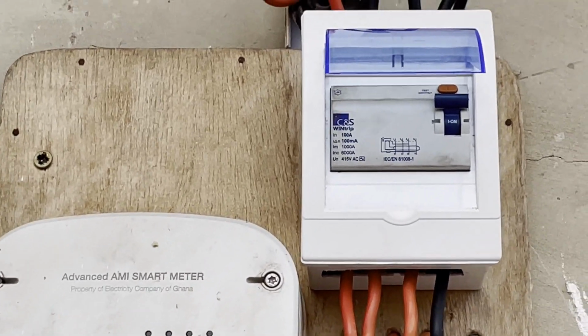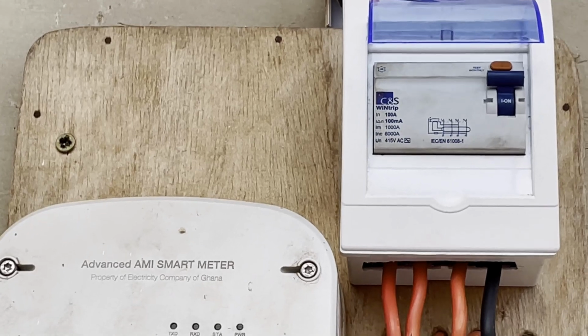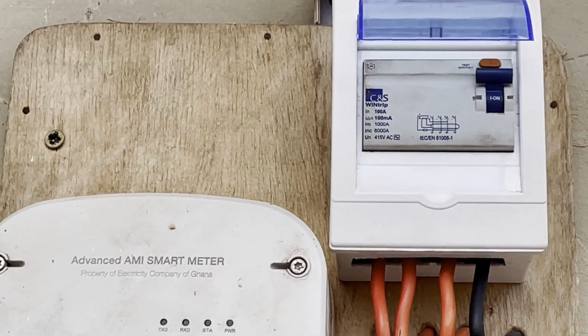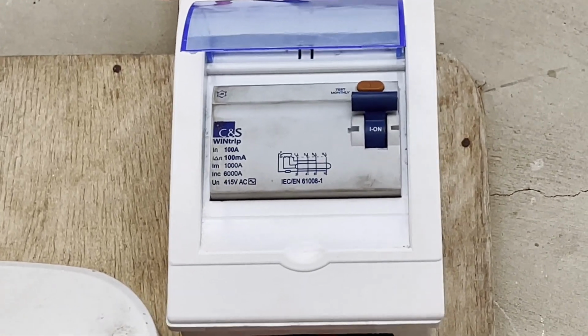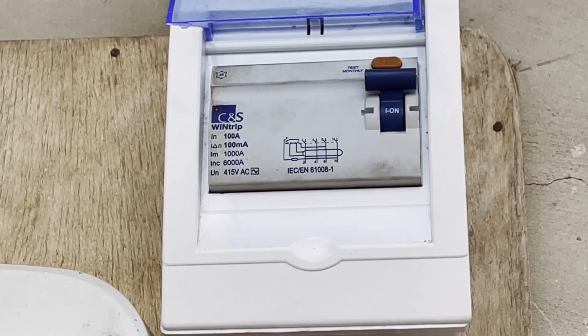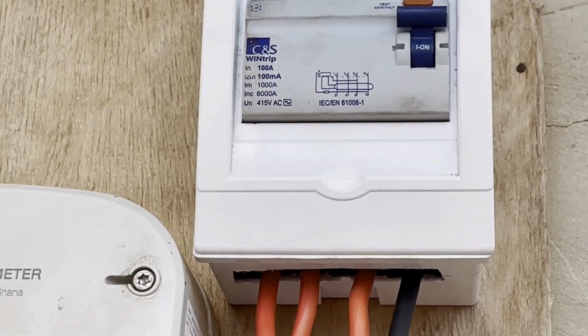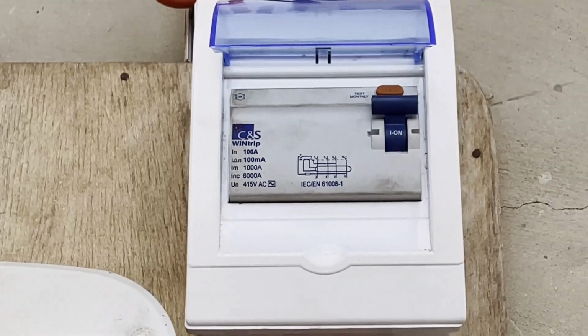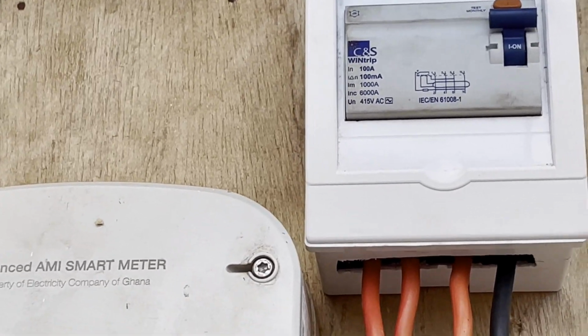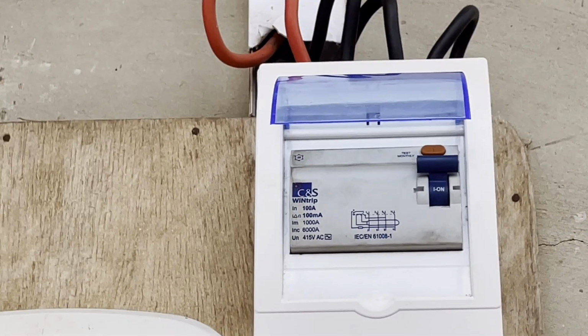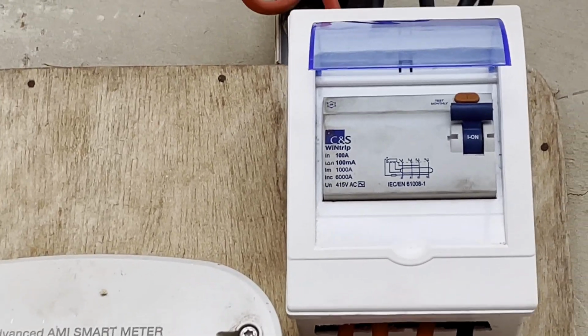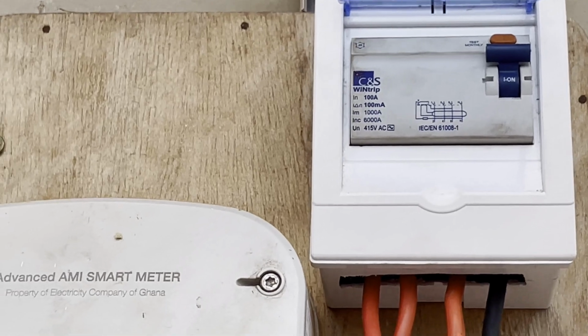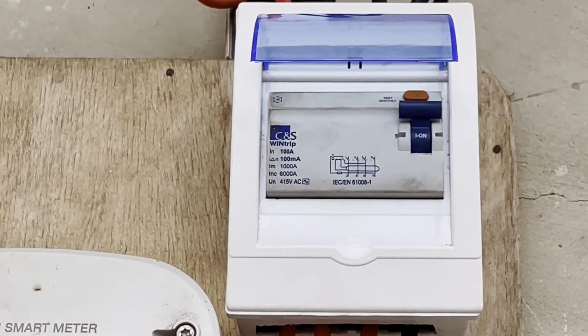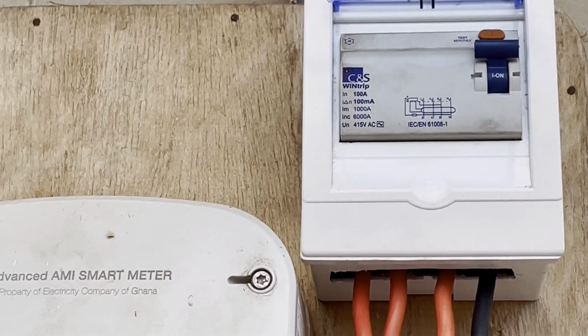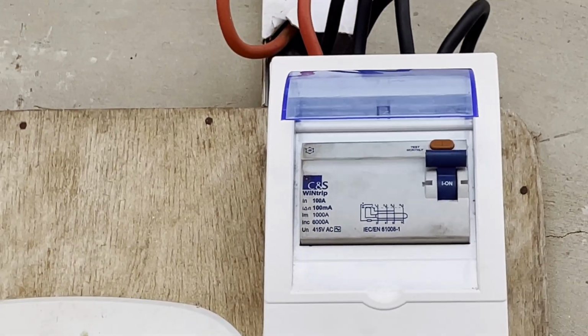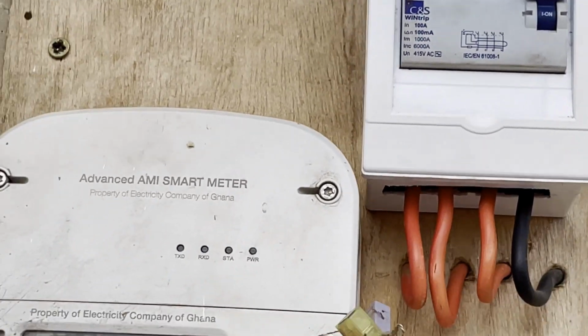So what I would say is the minimum should be 100 milliamp sensitivity. As you can see, that's the minimum sensitivity - that's the second line I'm talking about, below the 100 amp. That's the ideal figure. But obviously, if it nuisance trips on you, depending on what's in your home, you can go the next size up, which would be a 200 or 300 milliamps. But start with 100, and let's hope that works okay for you.